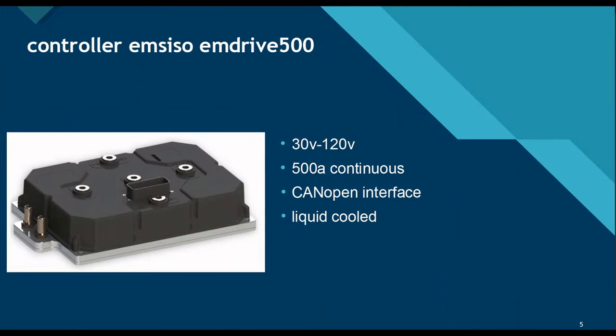The motor manufacturer recommended using the Emsiso EmDrive500 controller, and we chose this controller. It can run motors from 30 to 120 volts and give 500 amps continuously. It has an CANopen interface for adjustments, configurations, and to see all data online. It also has liquid cooling possibility, but we aren't using it.